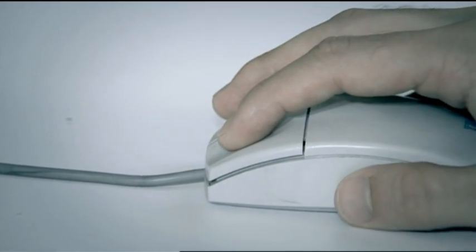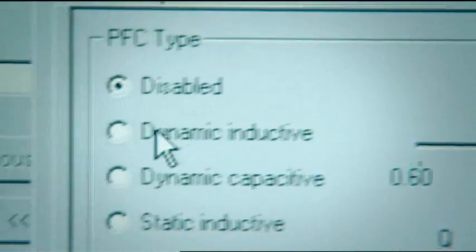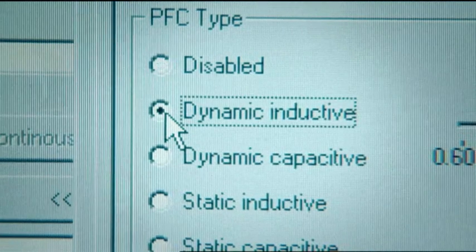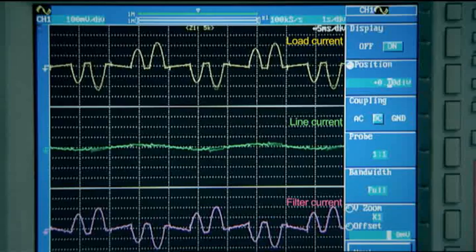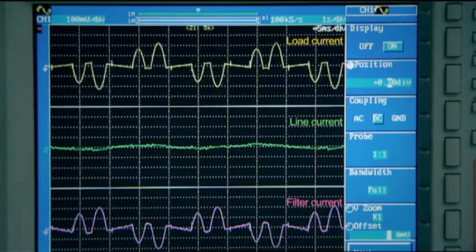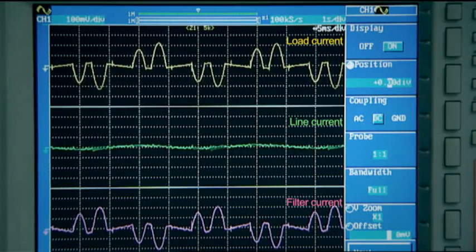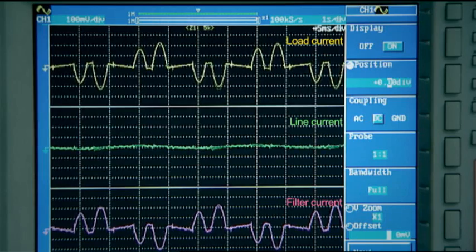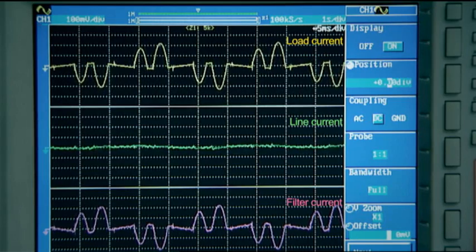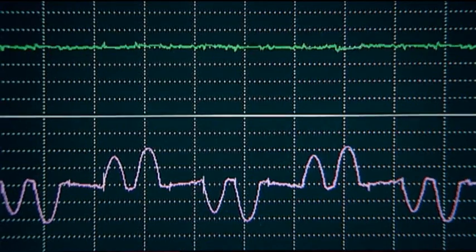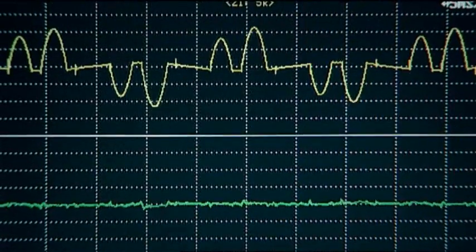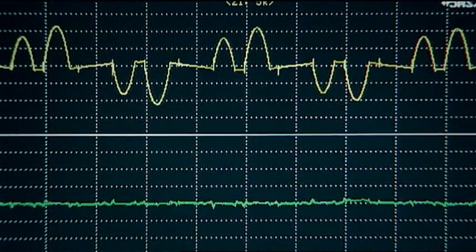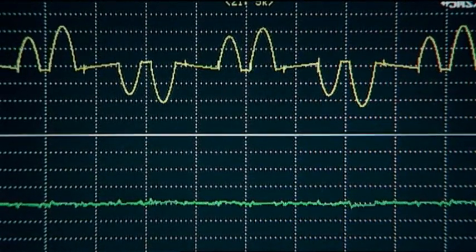The filter can also be programmed to compensate reactive power. This can very easily be done from the computer or the PQF manager filter user interface. Since the fundamental line current is mainly reactive, the fundamental current will disappear from the line.